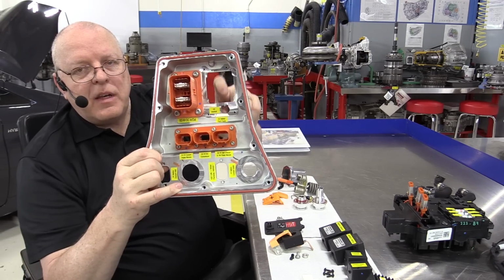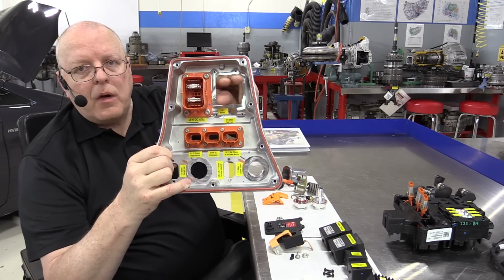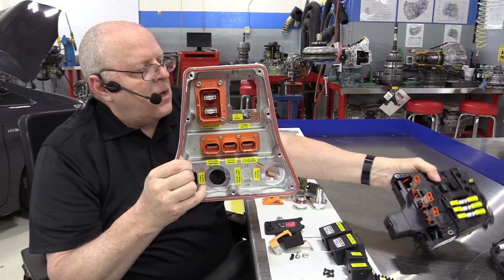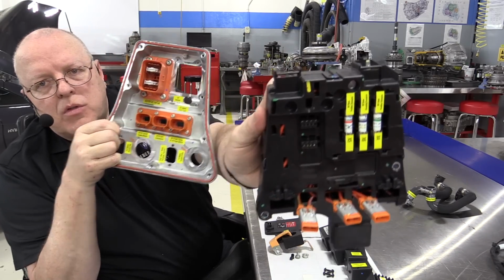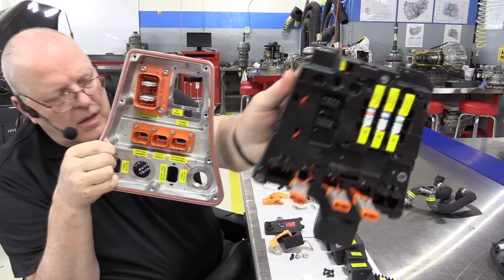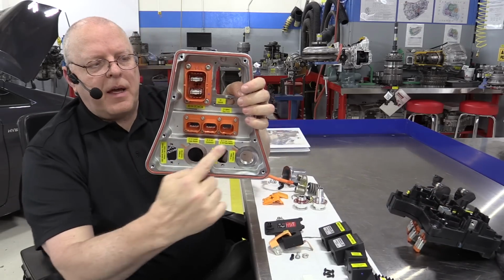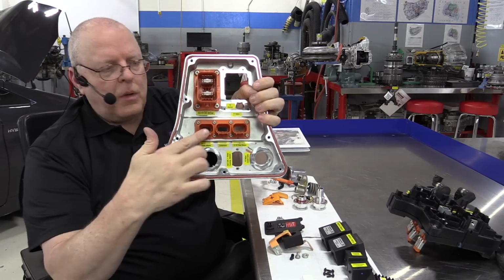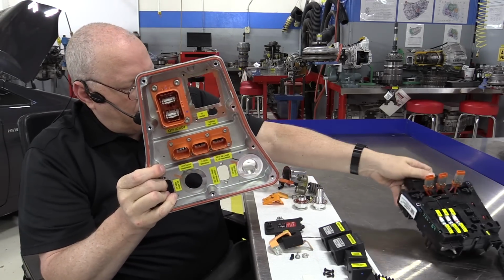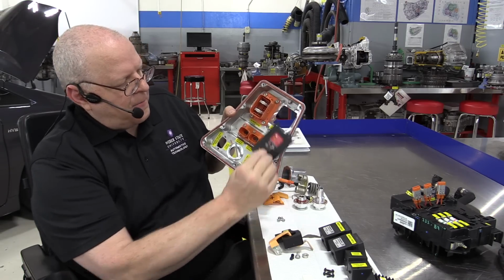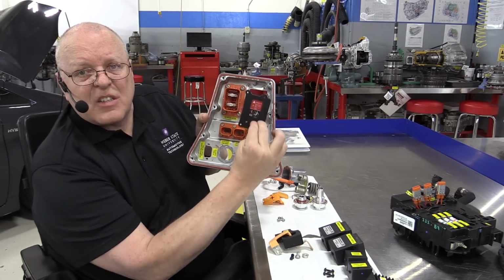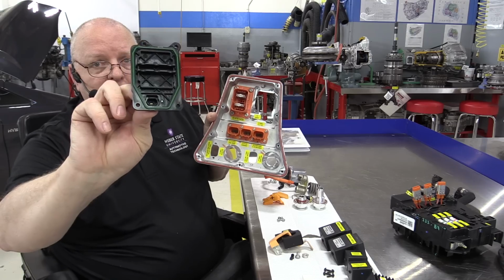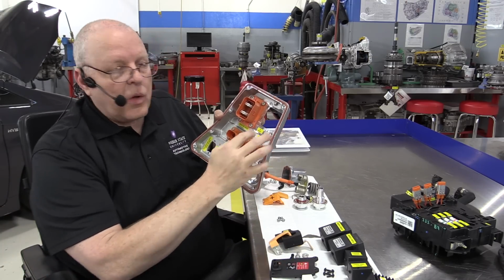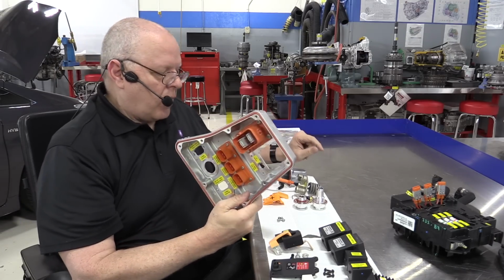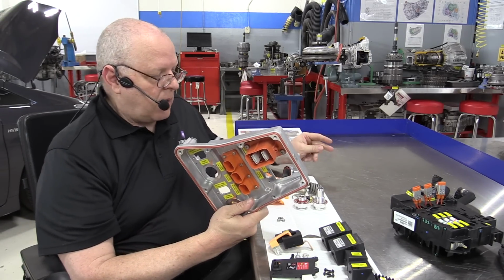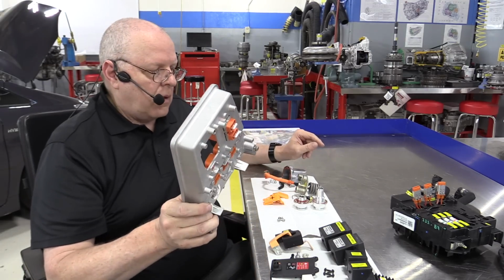Right here is an interlock circuit, because this hole right here is where we access 3 high voltage fuses that protect the circuits connected to these 3 electrical connectors right here. And if we take the cover off to access those fuses, there's an interlock circuit in there, a 2-terminal circuit, that will open up the contactors if they were closed, which they shouldn't have been anyway, but it's just a safety related item.